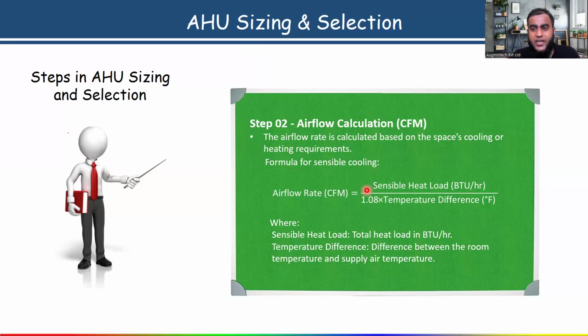Latent heat is what? Latent heat is generally related to moisture removal. So we don't need to consider that here while calculating airflow. That is why in the formula it is clearly written to calculate the airflow CFM. The formula is sensible heat load divided by 1.08 times the temperature difference. Is it clear now? All of you, let me know, please. Just give me a reply.